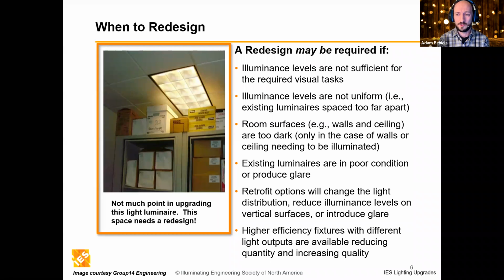If there's really poor uniformity in some spaces, where they've moved in furniture or desks, someone's not getting light, you definitely need more fixtures there. On the flip side, you may have older offices designed for higher lumen depreciation, since maybe they were built at a time when there was smoking in the offices, expecting a lot of depreciation in output. Now, simply replacing straight with a new T8, new lens, or a new LED tube, you might see almost too much light. So you may need to delete fixtures in that case.